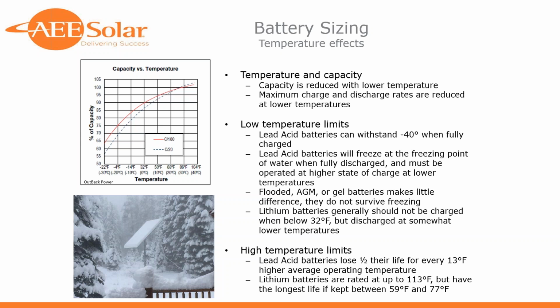And then there are low temperature limits on the lithium batteries that are fairly hard limits. If you try to charge most of the lithium batteries at below freezing, it affects the chemistry in a way where it plates the lithium out on one of the active materials and damages the battery permanently. So lithium batteries really cannot be run at a lower temperature than freezing. Although some of them actually have heaters in them to prevent that, but of course that cuts into your efficiency and your economics.